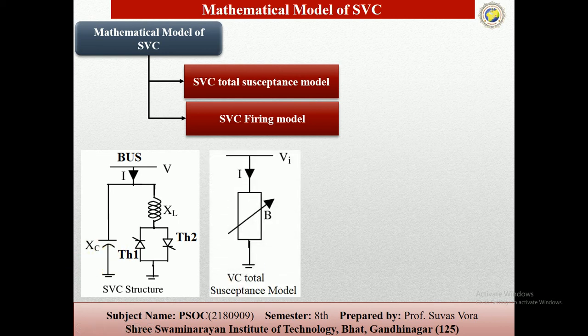Then after the SVC total susceptance model, there is the firing angle model, with equivalent reactance which depends on the changing of the thyristor firing angles and is made up of the parallel construction of the thyristor controlled reactors. This one is the equivalent admittance and the fixed capacitor. You can see here we can use the variable thyristor control.